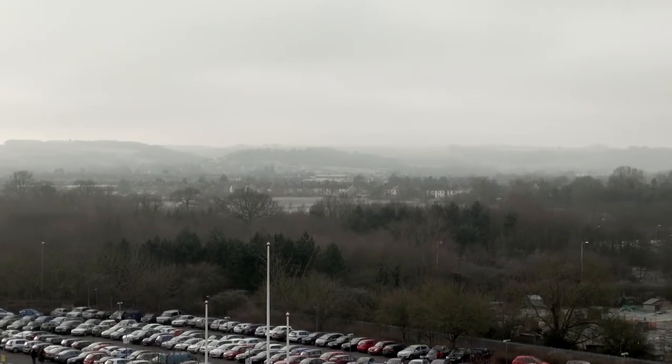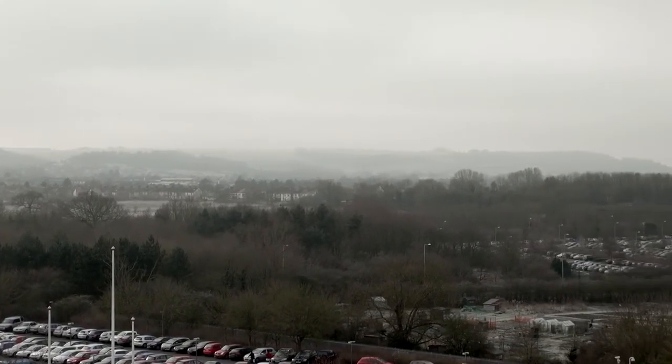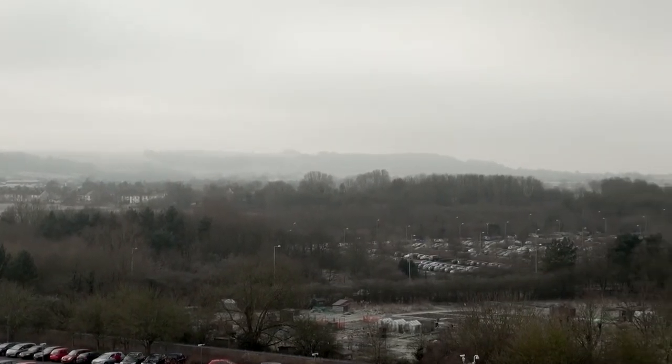One of the big things we did at this building, as you see, it's a big tall building, and it pumps hot water to all the toilets 24/7. The reason for that is for various water conditioning reasons. We did a few experiments where we could turn the water off for so many hours of a night, and then switch it on early morning before people came in to work to make sure that the water was in the right condition. So the water now isn't 24/7 constant, it's on a timed circuit. That was a very simple exercise of building management control, setting time clocks.